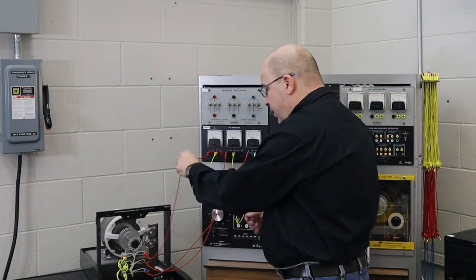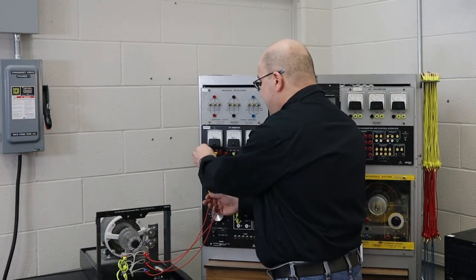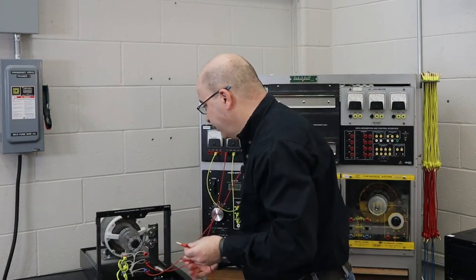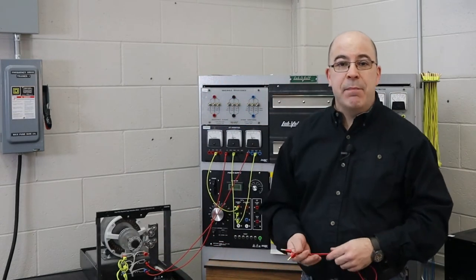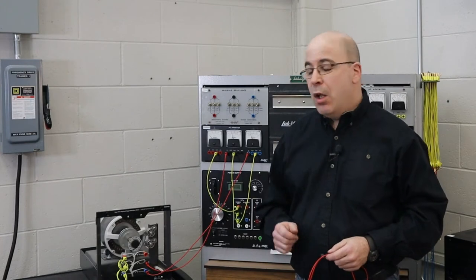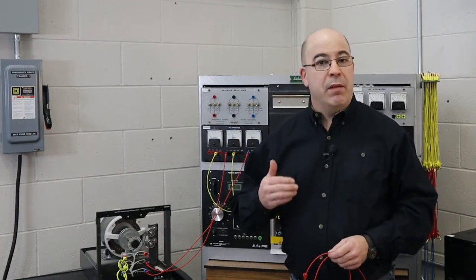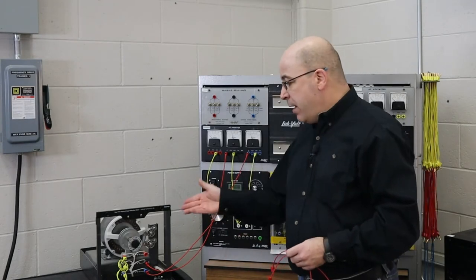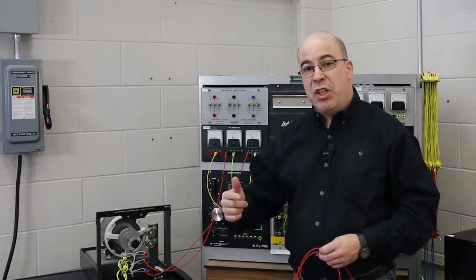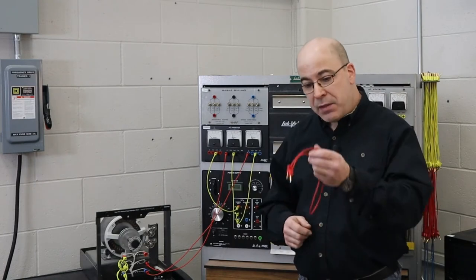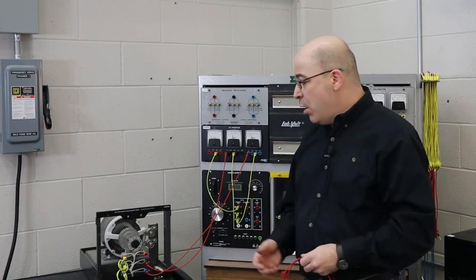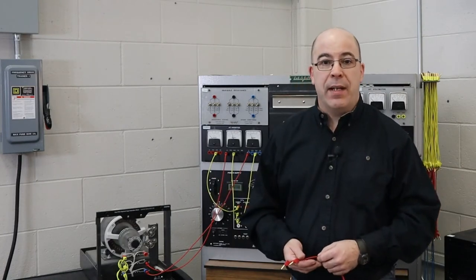If I disconnect the red phase, my three phase motor continues to operate. What it is is that this operates on the principle of a rotating magnetic field. If the rotor is in operation or is rotating at the time that we lose a phase the motor will continue to operate.